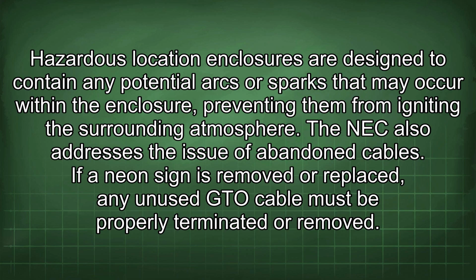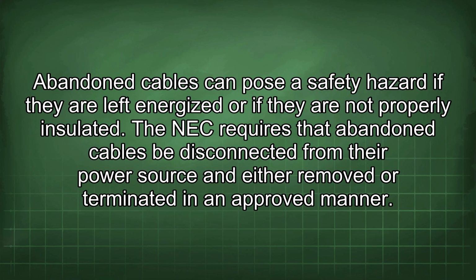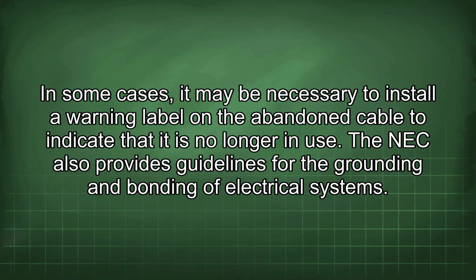The NEC also addresses the issue of abandoned cables. If a neon sign is removed or replaced, any unused GTO cable must be properly terminated or removed. Abandoned cables can pose a safety hazard if they are left energized or if they are not properly insulated. The NEC requires that abandoned cables be disconnected from their power source and either removed or terminated in an approved manner. In some cases, it may be necessary to install a warning label on the abandoned cable to indicate that it is no longer in use.